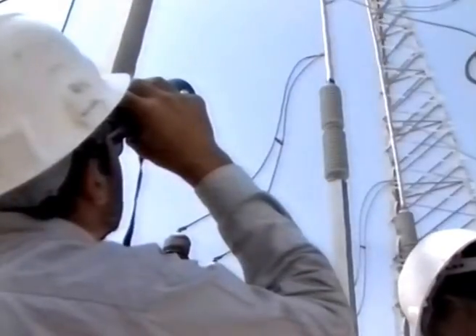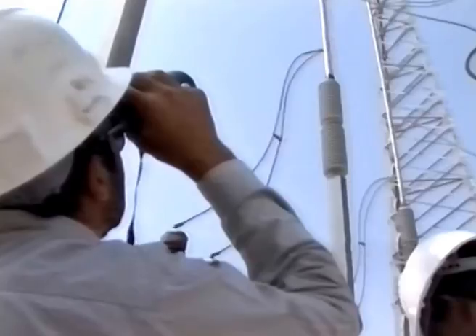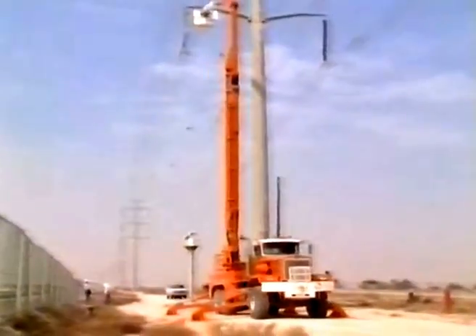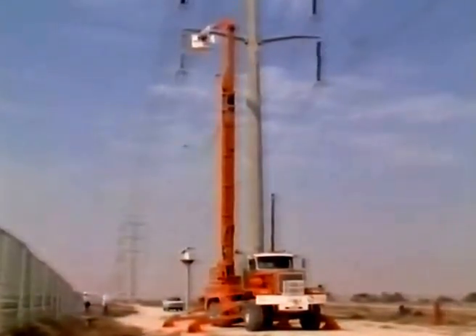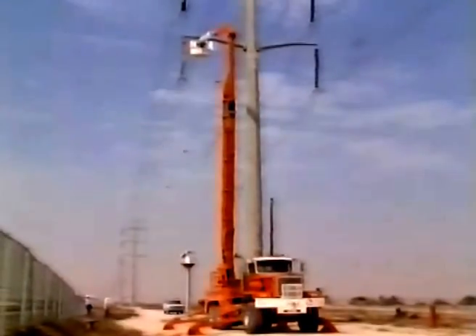An inspection may be warranted on various overhead transmission lines that have had numerous undiscovered forced outages. A high patrol is usually implemented when a ground patrol finds no cause for the trip. A bucket truck is used for this purpose. The aforementioned frequencies are recommended guidelines.